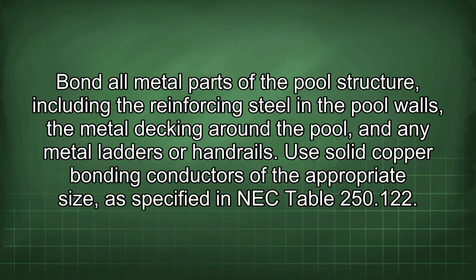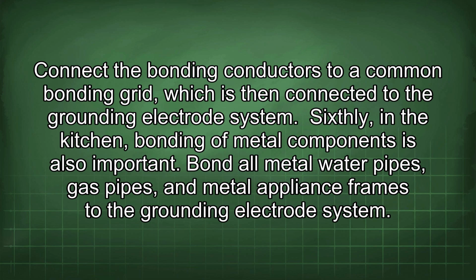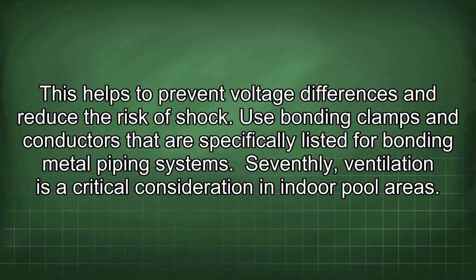Bond all metal parts of the pool structure, including the reinforcing steel in the pool walls, the metal decking around the pool, and any metal ladders or handrails. Use solid copper bonding conductors of the appropriate size, as specified in NEC Table 250.122. Connect the bonding conductors to a common bonding grid, which is then connected to the grounding electrode system. Sixthly, in the kitchen, bonding of metal components is also important. Bond all metal water pipes, gas pipes, and metal appliance frames to the grounding electrode system. This helps to prevent voltage differences and reduce the risk of shock.